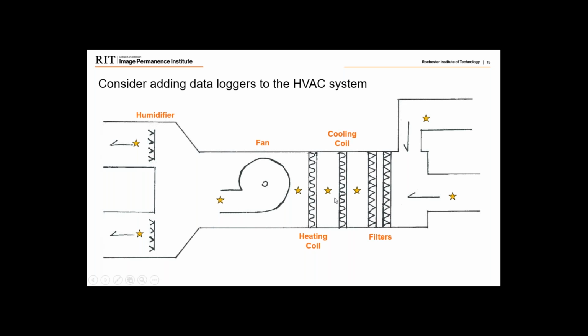After the cooling coil, we could either put it - this is an either/or, not both - after the heating coil or after the fan in the scenario. Again, looking for those pre-post conditions. We now know what the cool air is. After that, what kind of heating are we doing to that air? How much energy are we putting into that air? What's the temperature we're raising it to?